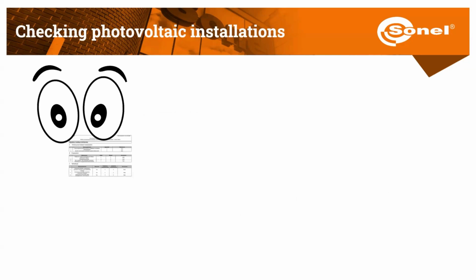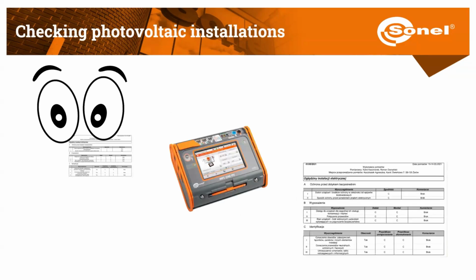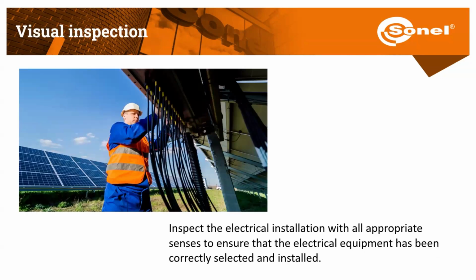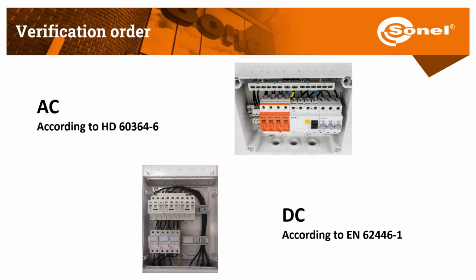We should remember that verifying the installation is not only about taking measurements. Verification includes 3 main steps: visual inspection and paper checks, taking measurements, and preparing documentation and a report after the inspection. Visual inspection includes checking if all the system components are correctly selected and installed, and if there is no visible damage to any parts. We begin the verification of the PV system by checking the AC side first, then the DC side.